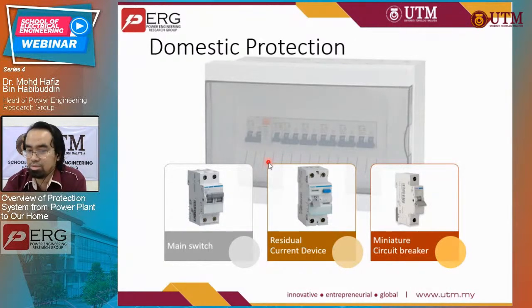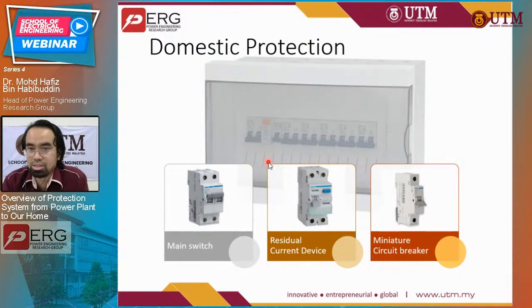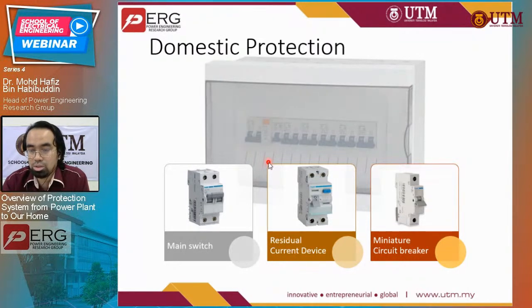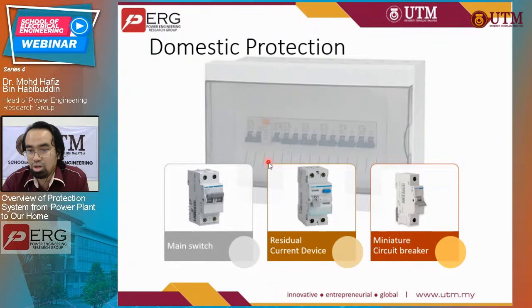The last part will be on domestic protection. I'm going to introduce several protective devices available in your home. You are familiar with the distribution box in your home — it basically has three equipment inside. The first one is the main switch — its function is to isolate your network from the supply of electricity when you want to do some wiring or maintenance. The second device is called the residual current device, which detects a leakage in your system. If there is a leakage, the current in the live and neutral will not be the same, causing the residual current device to trip.